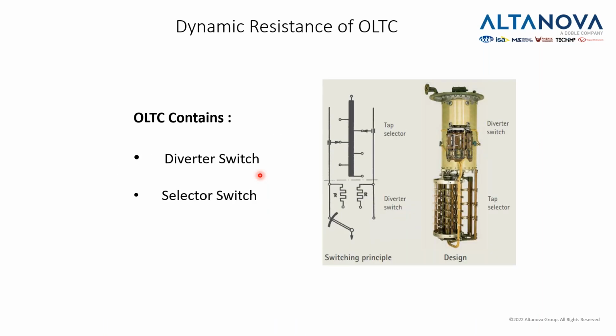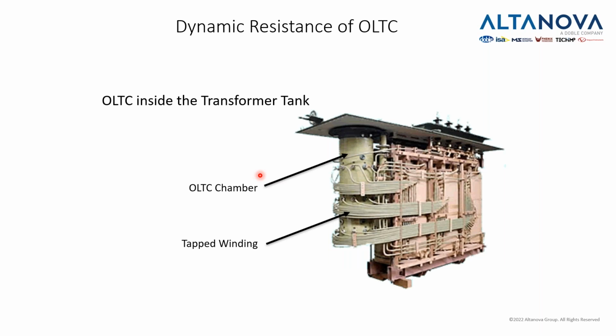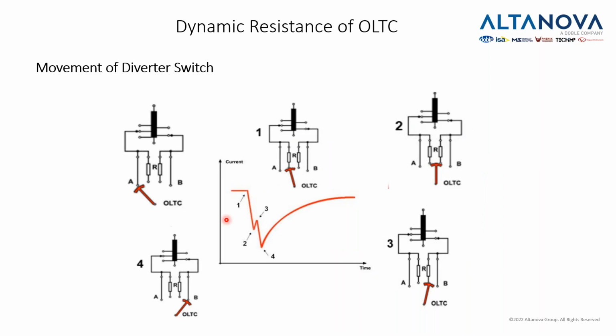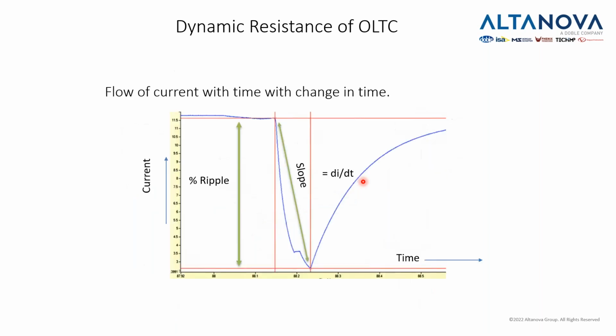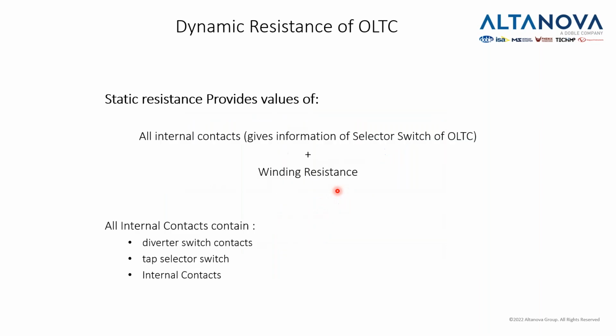Now, if we want to measure the resistance not only when the tap changer is still, but while the tap changer moves, then we will do a dynamic resistance of on-load tap changer. As the tap changer moves from position 1 all the way to position 4, it creates this specific form. If you measure the resistance for every change of tap changer, you will obtain a graph like this. Each graph should be the same from each position. If they differ, and what we measure is the ripple, which you can see here, and the slope, if these numbers differ from each other, then we should look into this tap changer a little bit more. So, dynamic resistance of on-load tap changer.